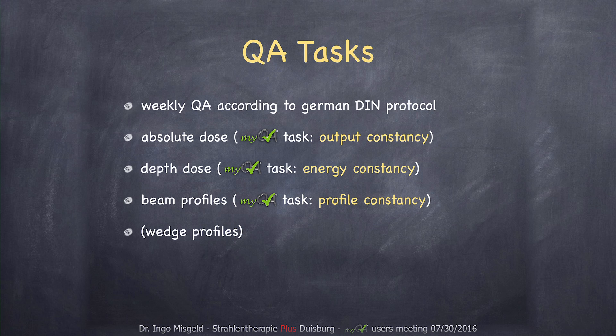This is weekly QA. We measure absolute dose, depth dose, and beam profiles. For this we use the MyQA tasks: output constancy, energy constancy, and profile constancy. There's also a MyQA test called wedge profiles, but we still haven't used this — we're going to implement it in the next time.